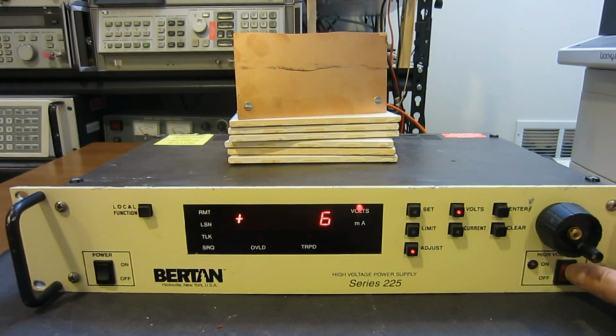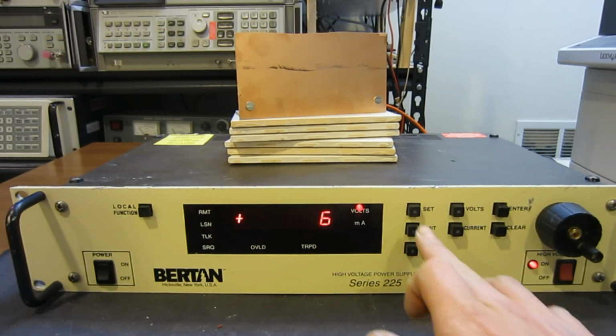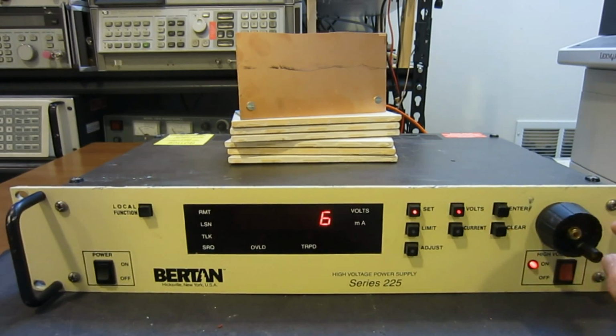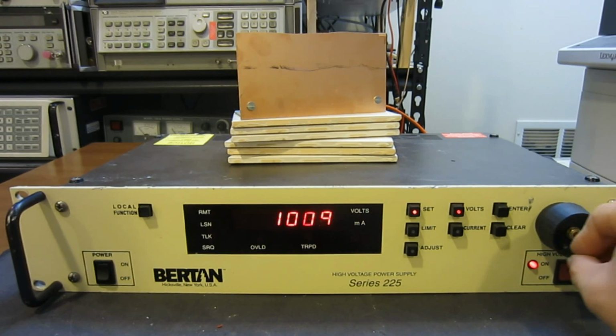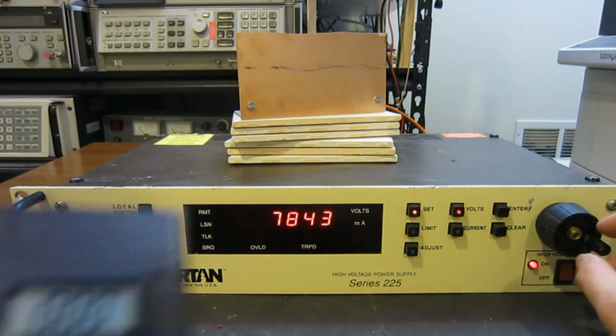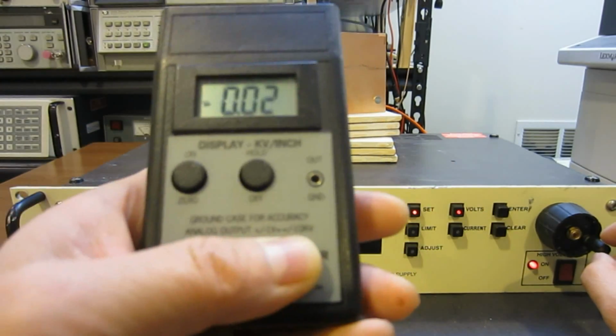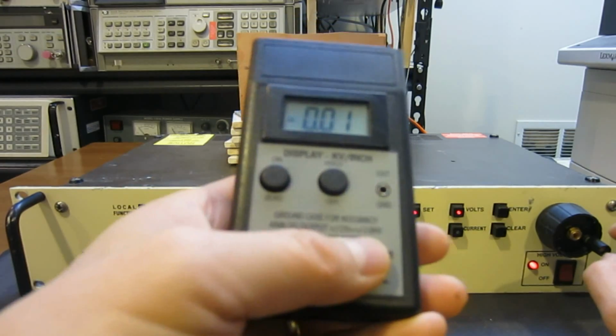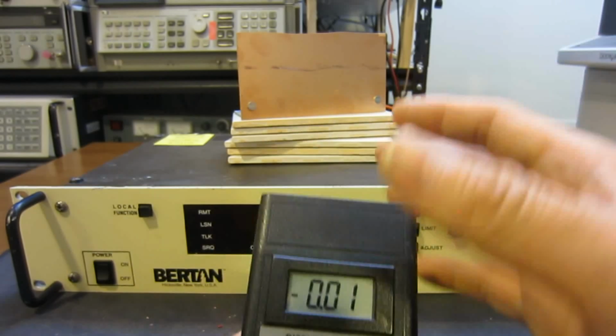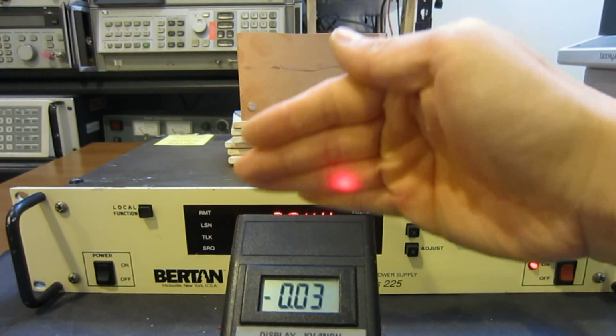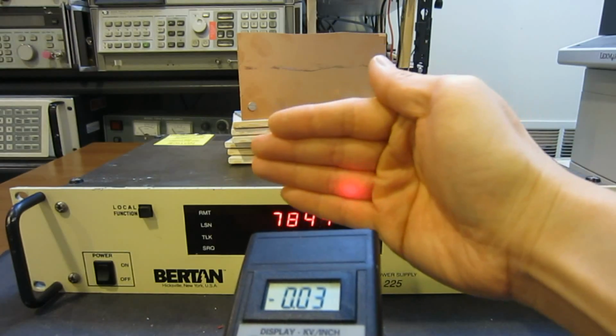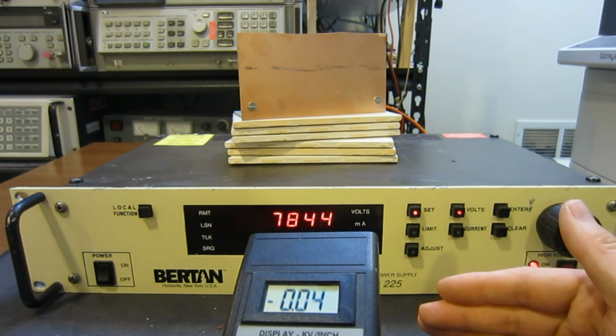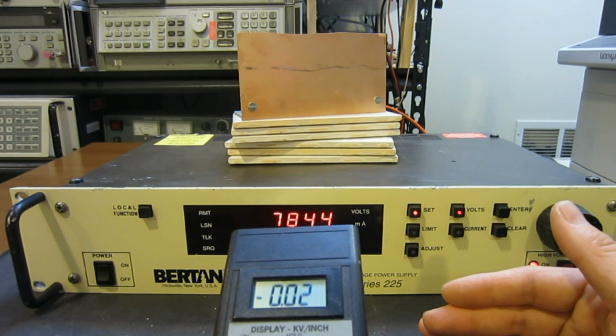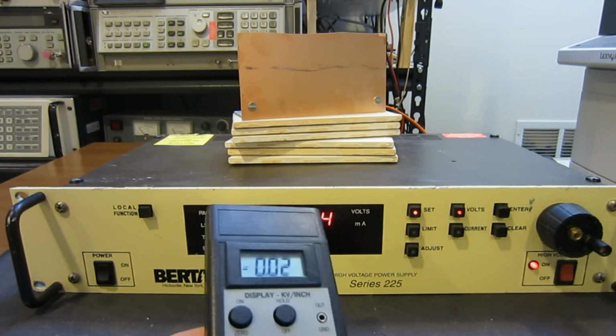And now I'm going to turn on the high voltage and set it to 10,000 volts. This time we're going to use a set functionality. When you are setting the voltage, it actually doesn't output that voltage yet, so we can precisely set what we want. This time it is 10,000 because that's the maximum this unit is capable of. It's more of a discharging hazard than what this is capable of, because as the voltage goes higher, the distance required to discharge becomes larger. You have to put this 1 inch in front of the object to measure, so in order to eliminate the discharging hazard, it is limited to 10,000 volts.